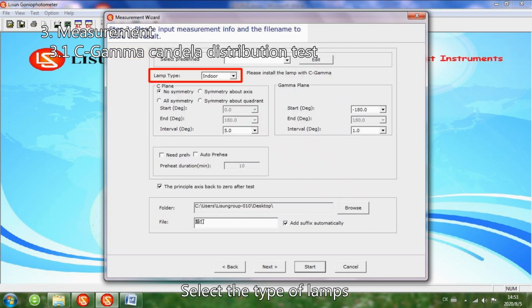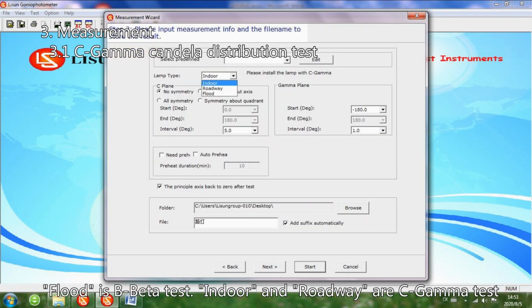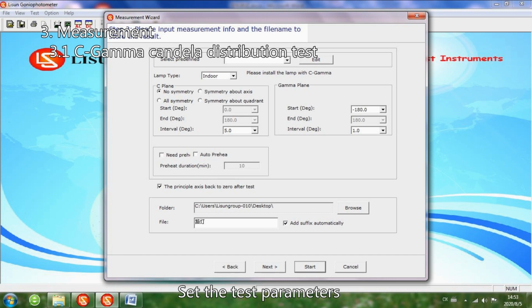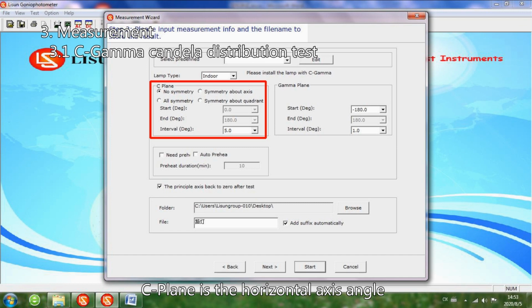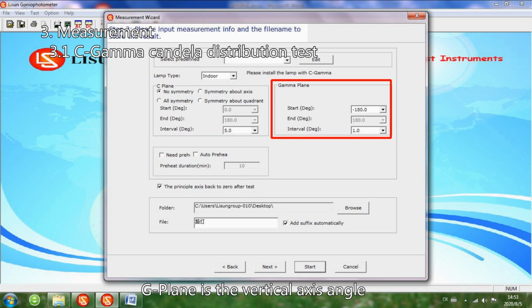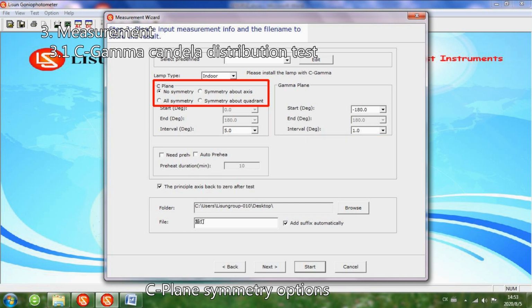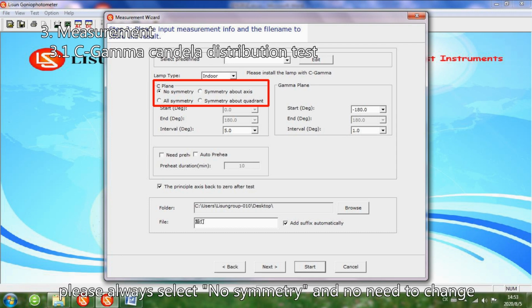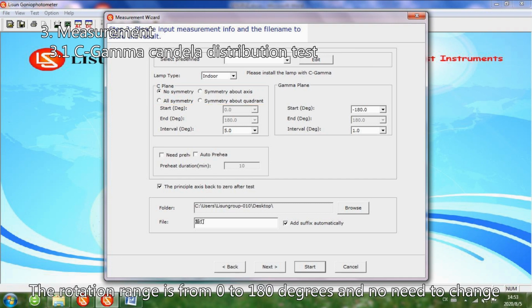Select the type of lamps. Flood is B beta test. Indoor and roadway are C gamma test. Set the test parameters. C plane is the horizontal axis angle. G plane is the vertical axis angle. For C plane symmetry options, if there is no special requirement, please always select no symmetry and no need to change. The rotation range is from 0 to 180 degrees and no need to change.